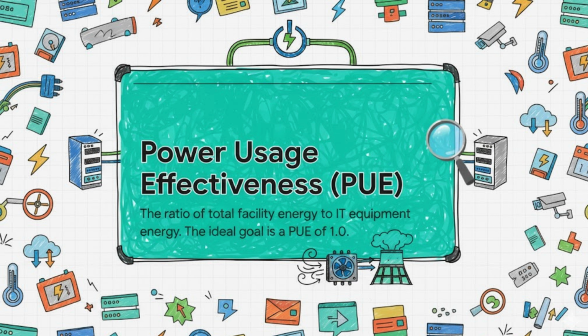By far, the most widely used metric in the industry is power usage effectiveness, or PUE. It's a pretty simple ratio: you take the total energy the facility uses and divide it by the energy used by just the IT equipment. A perfect PUE would be 1.0, meaning zero overhead for coolant or power distribution. Of course, that's impossible, but the goal is always to get as close to 1.0 as you can.